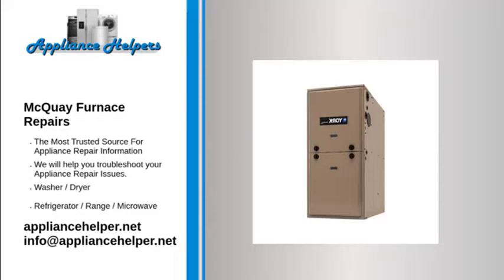E. If voltage is satisfactory at terminal 6 and L2 and terminal 4 does not become energized after 10 seconds, and pressing the safety reset button has no effect, replace the RM7897A.